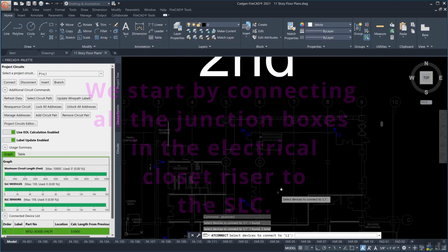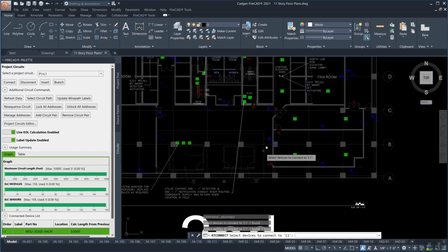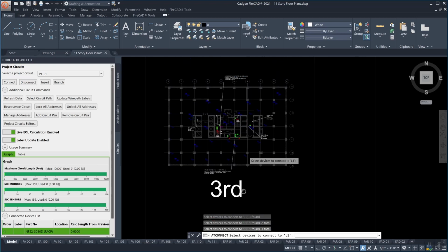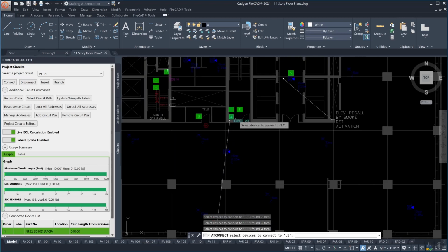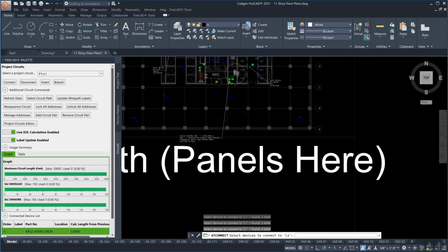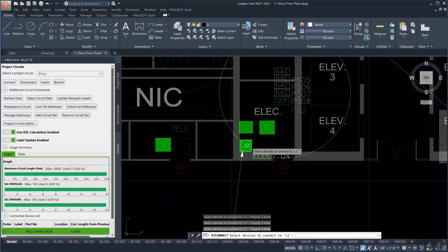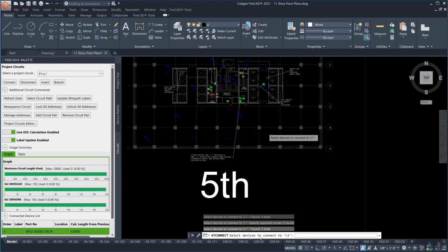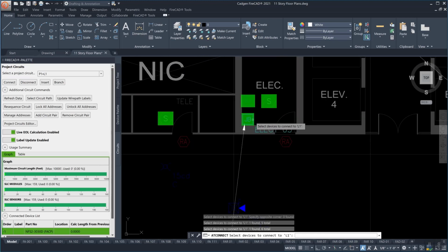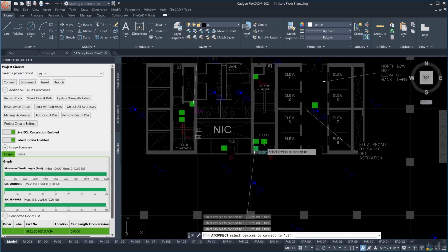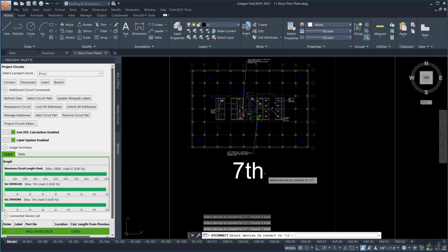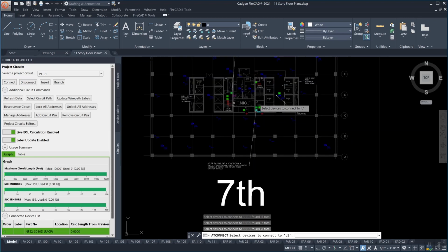We start by connecting all the junction boxes in the electrical closet riser to the SLC. We work our way all the way up the building, one click at a time, in order to get the junction boxes in the proper order on the SLC circuit.